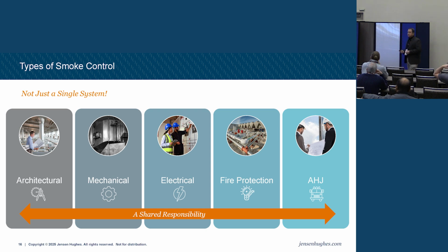Electrical systems. So one big challenge we're dealing with right now is a jurisdiction just came in and said, I need smoke control in this building. Their electrical cannot handle the load of all the air handlers kicking on at one time to go to an exhaust mode. So they want to stage the equipment on. I can't stage equipment on. There's a time requirement on how fast I have to be in a smoke control mode. So now they're looking at electrical upgrades.